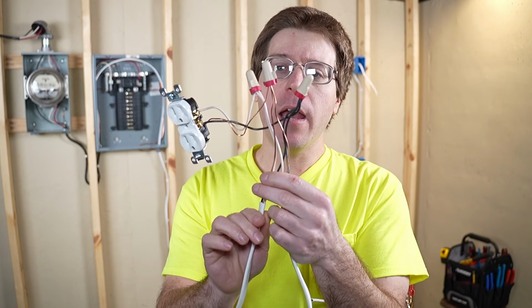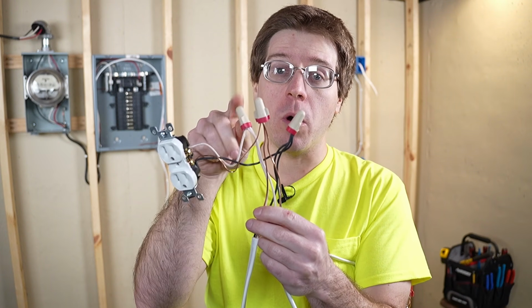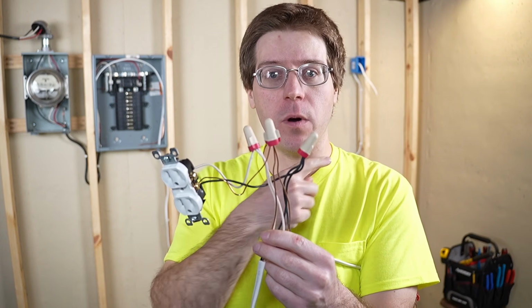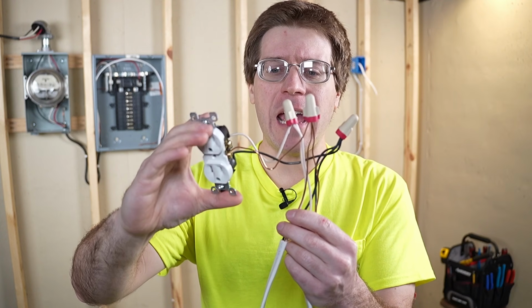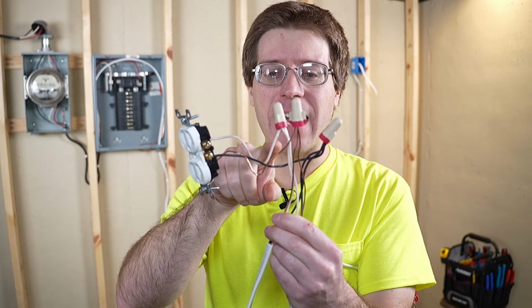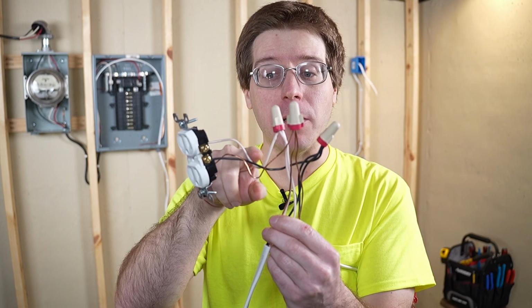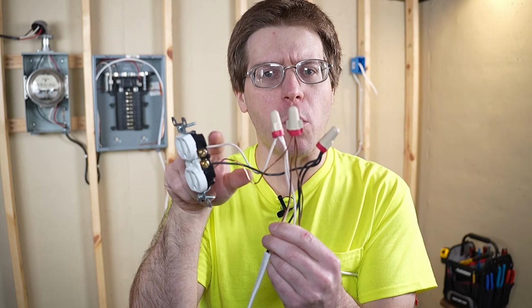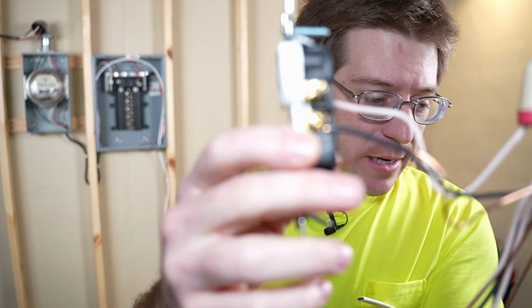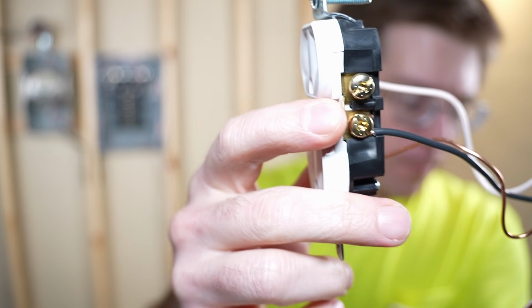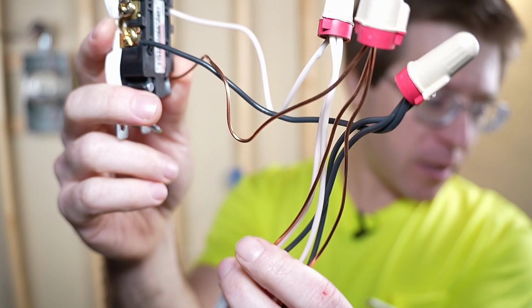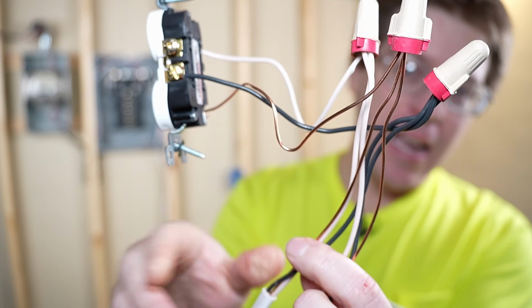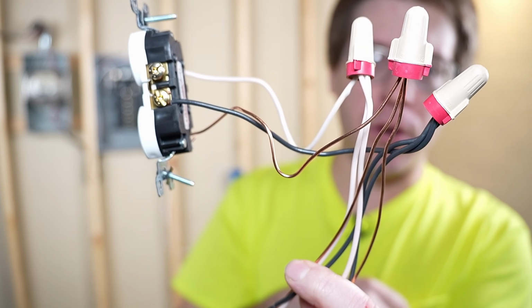We're gonna have wires coming into the box, our in and out right here, and we're actually gonna use wire nuts, or I'll also show Wagos in one of the boxes. We'll also have a set of wires that don't leave the box, called pigtails. So we're going to land only one wire on each receptacle, but then they'll go to a set of wire nuts, and everything's going to be wire nutted together right here.